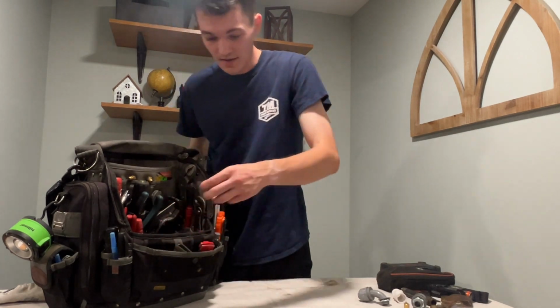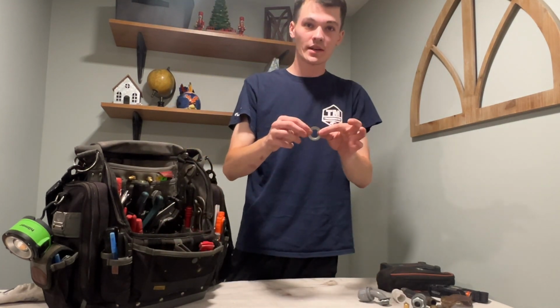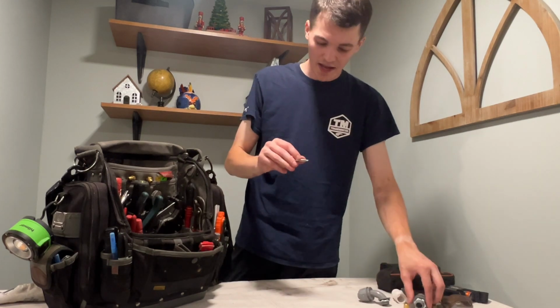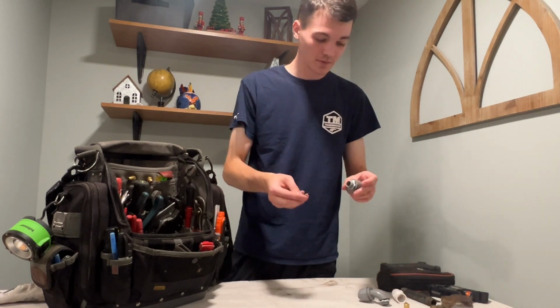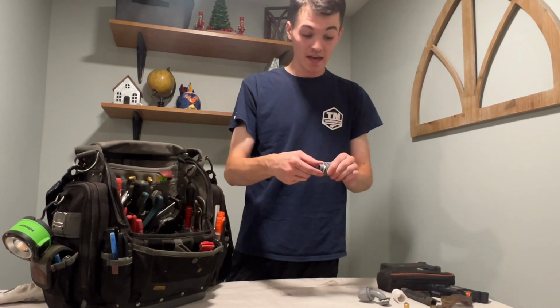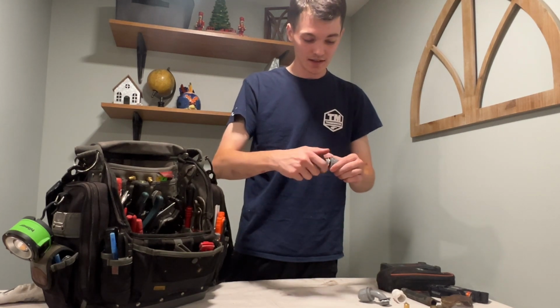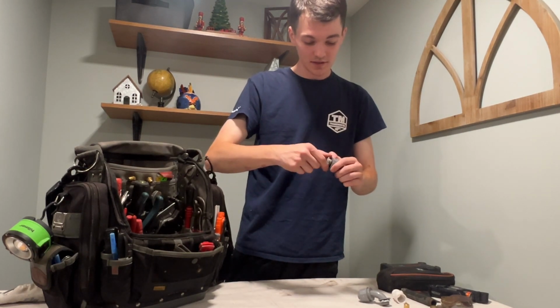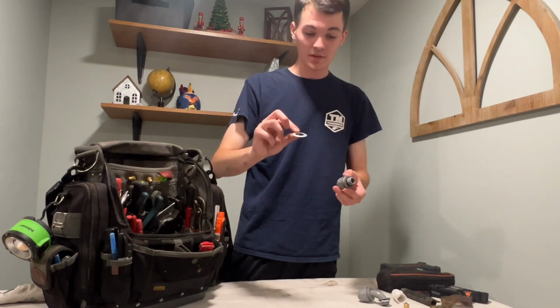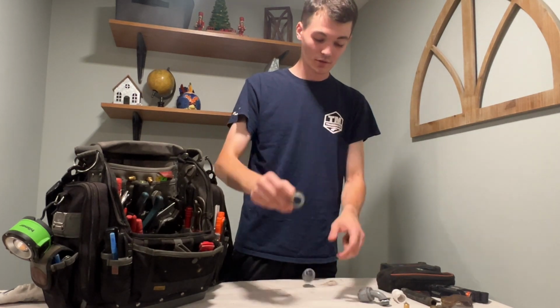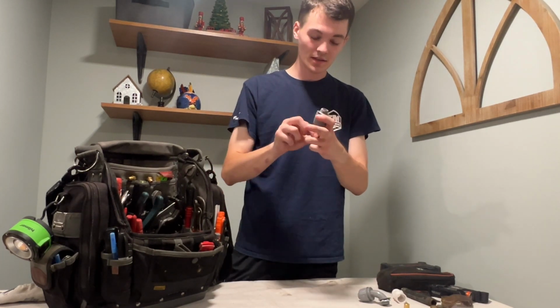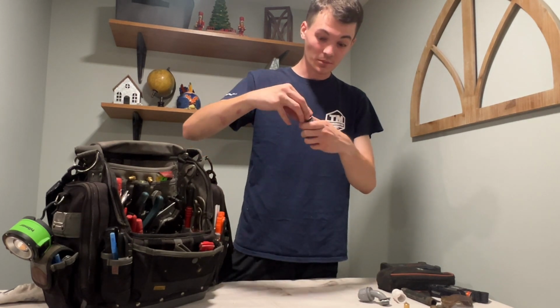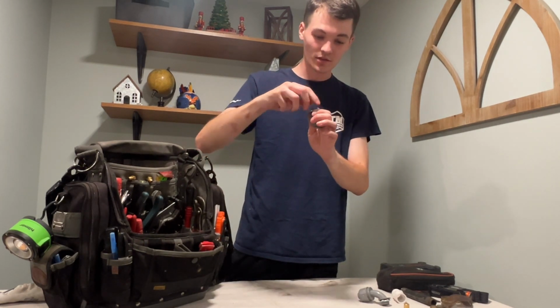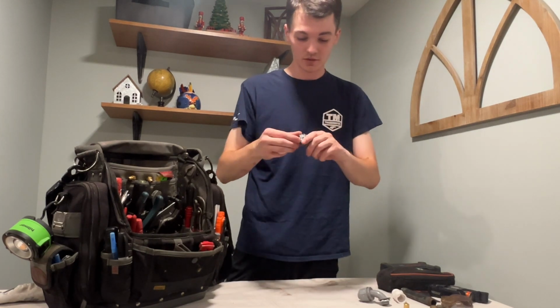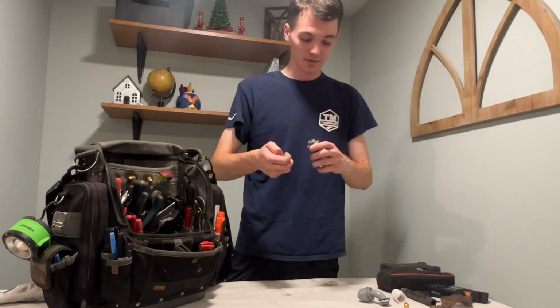I keep a 3/4 to 1-inch adapter, or 1/2 inch to 3/4 adapter. We use these 1/2 inch liquid tight connectors, but a lot of manufacturers have the 3/4. You could slip this over the hole, pop your connector through, and make it nice and tight. It'll be completely liquid tight and secure, and you don't have to worry about drilling a second hole or upgrading to the bigger size of liquid tight.